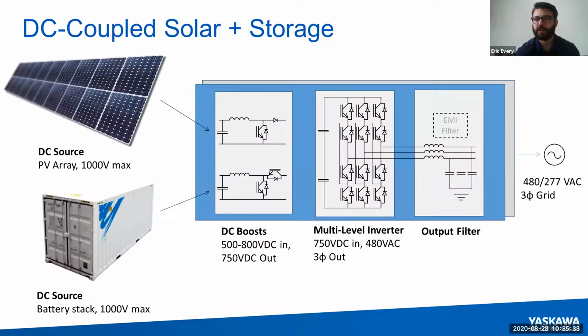So AC coupling refers to the two systems being connected on the AC side. That's in contrast to the DC coupled topology, where I put the batteries and the solar on the DC side of one inverter, and then have that one inverter manage all the inversion and export to the grid.